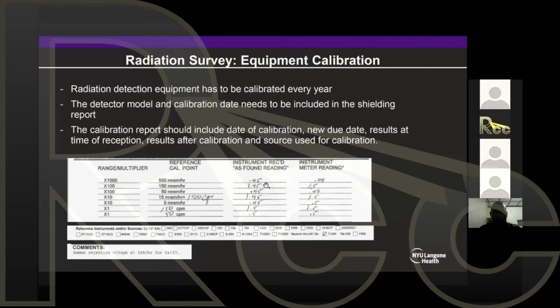When you send it for calibration, you're going to see, this is a screenshot from the neutron detector. They perform measurements before calibrating the detector. So you can see there's not that much difference, like 0.45 to 0.5. That's a good way to spot if your detector might have any issue, if suddenly you have a very strange number when you send it for calibration. And they include the source they use for calibration. And also, as I said, for neutron detectors, they verify that it's not going to respond to gamma radiation.